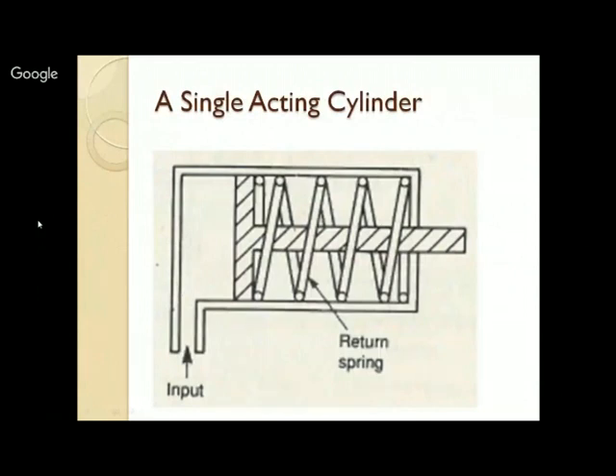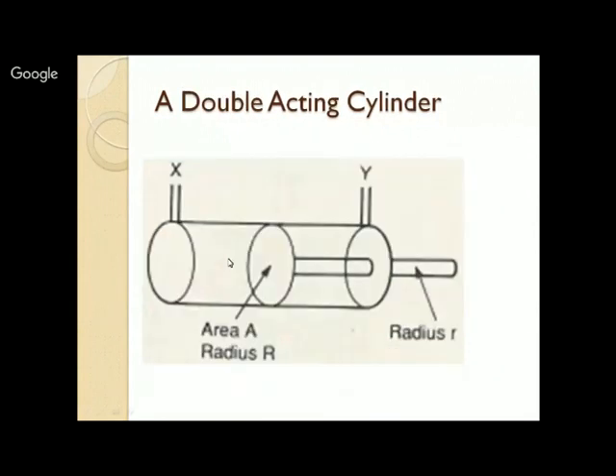A single-acting cylinder has a barrel with a piston and a spring on one side. Pushing air or oil in moves the piston forward; when the fluid is removed, the spring pushes the piston back. A double-acting cylinder has two ports — X and Y. To move the piston forward, fluid is pushed in through X and taken out through Y; to move it backward, fluid is pushed in through Y and taken out through X.